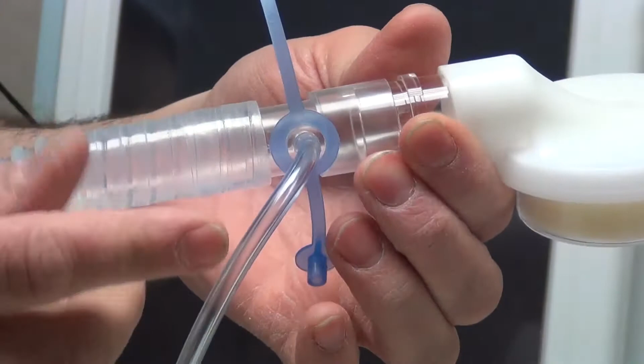If it doesn't seem to plug in, for example, oh no, it doesn't want to go, in the bag, if it's not connected to the end of this tubing, you'll find this little plastic piece. Just insert it into the end of the tubing and into your HME, and you're all set. If you look, you see these little blue rubber plugs here. You've got the clear tubing that's plugged into a port on this side. That must stay. And here's a plug for that if you were to unplug it, but in our circumstances we need this tubing, so we're not going to have it plugged.